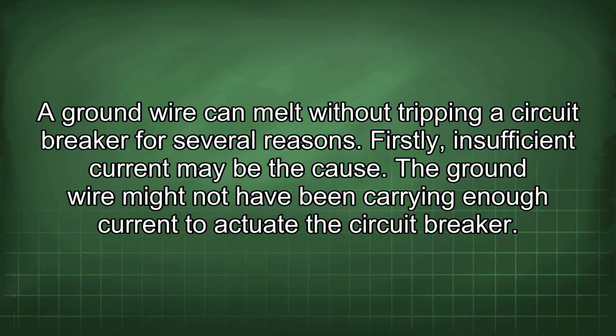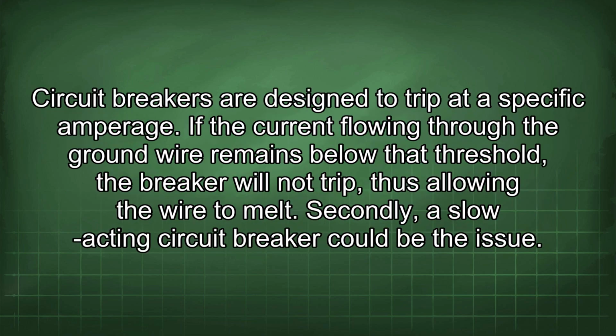A ground wire can melt without tripping a circuit breaker for several reasons. Firstly, insufficient current may be the cause. The ground wire might not have been carrying enough current to actuate the circuit breaker. Circuit breakers are designed to trip at a specific amperage. If the current flowing through the ground wire remains below that threshold, the breaker will not trip, thus allowing the wire to melt.